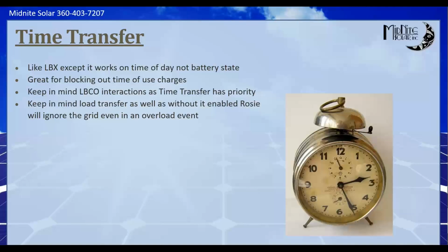The other thing that by doing that is you enable overload reconnect. What that is, if either leg of the Rosie overloads, it will force a reconnect to the grid as well. Because you set it for 7,000 watts, that's total wattage. If you put 5,000 watts on L1 and 0 watts on L2, you only have 5,000 watts of load. You will eventually overload the Rosie because you've overloaded one leg. And then what it does is it automatically reconnects to the grid as well. So that's something to keep in mind.